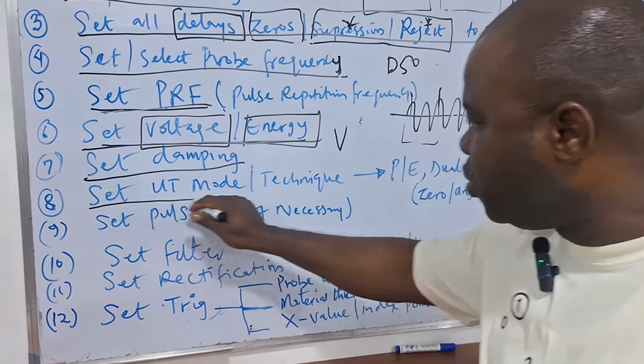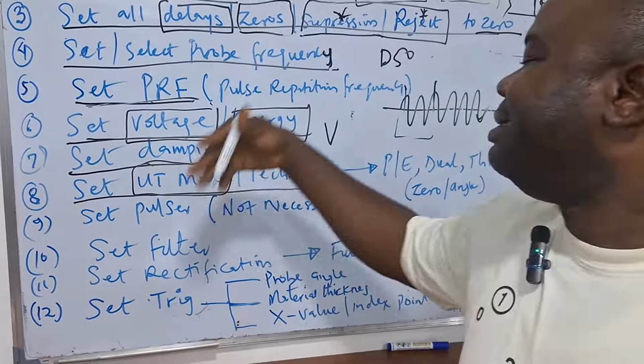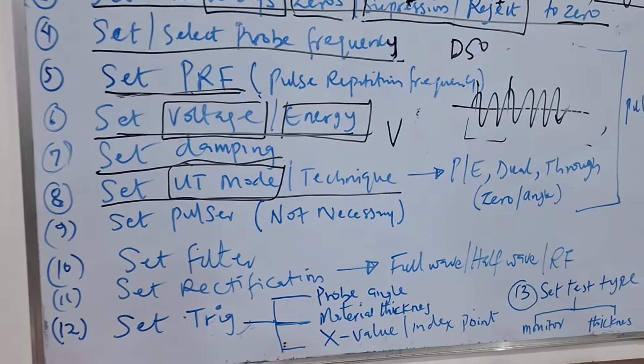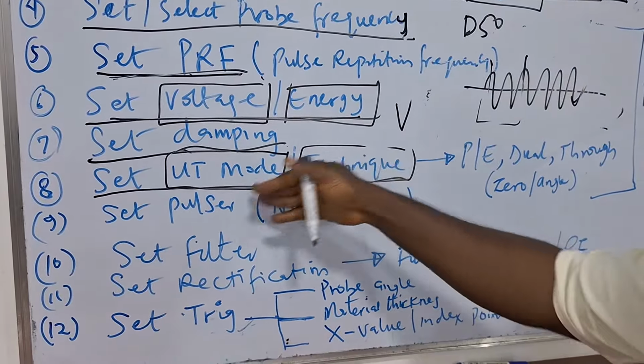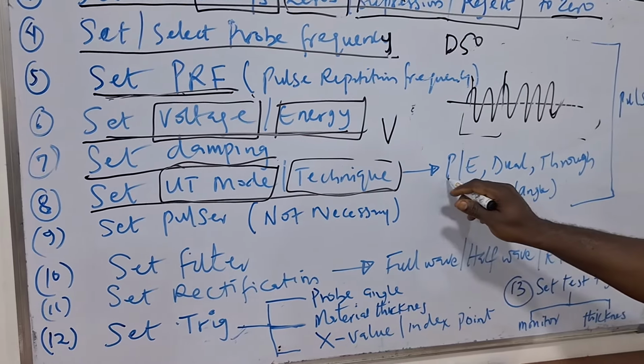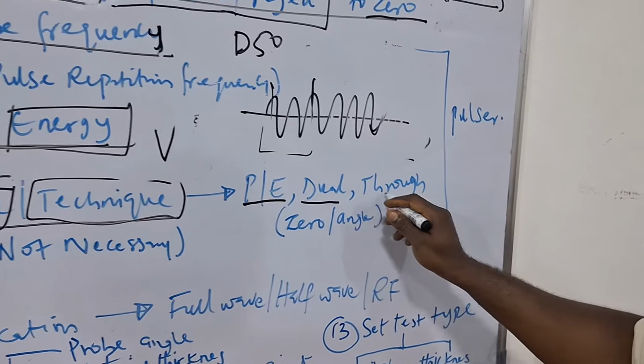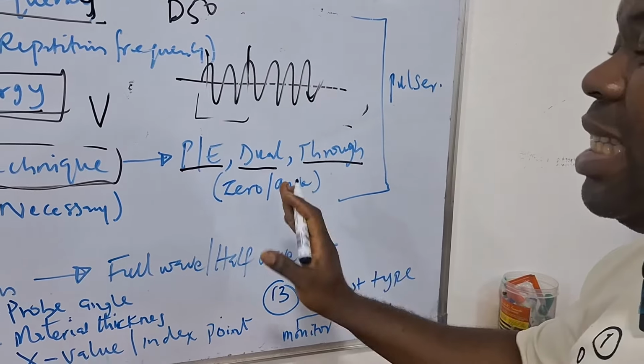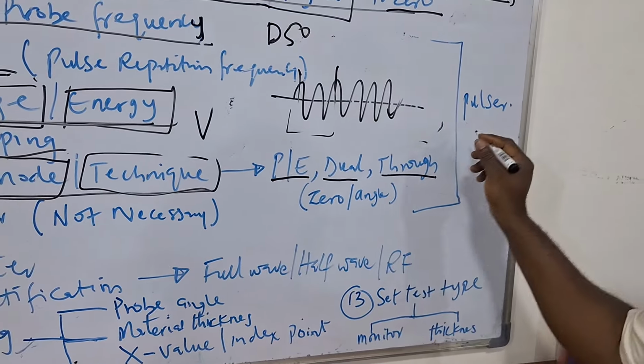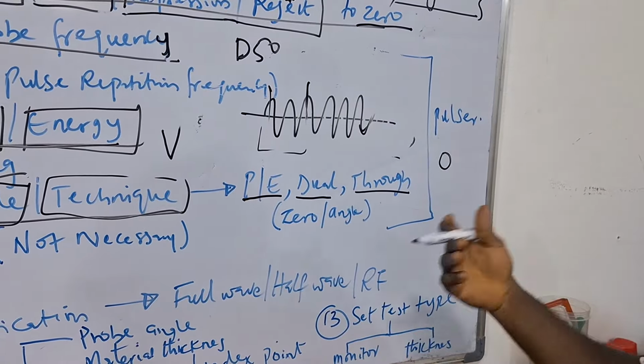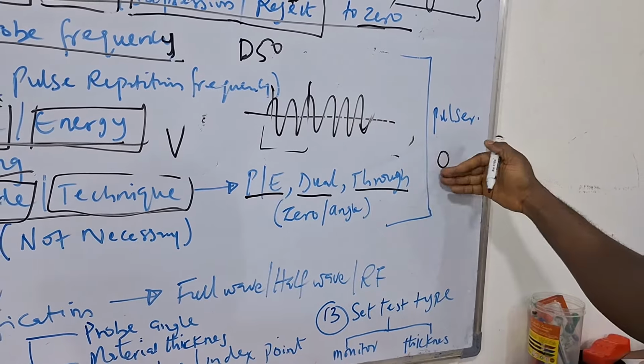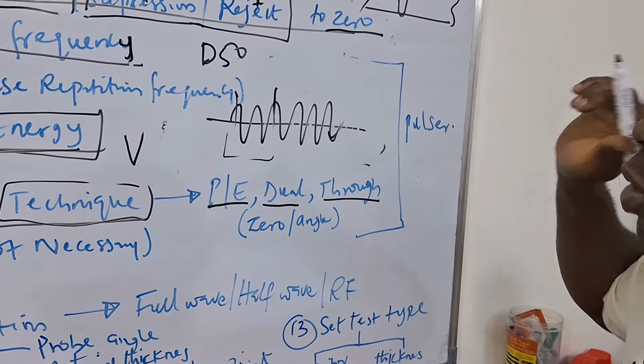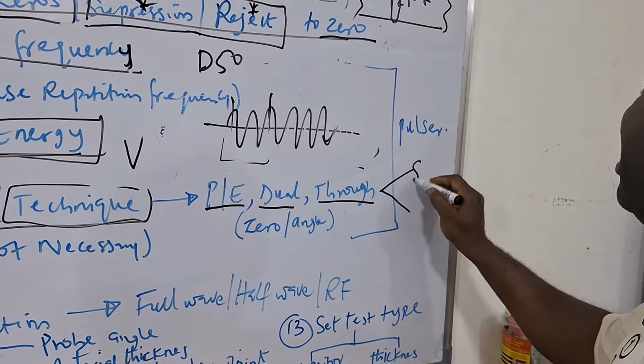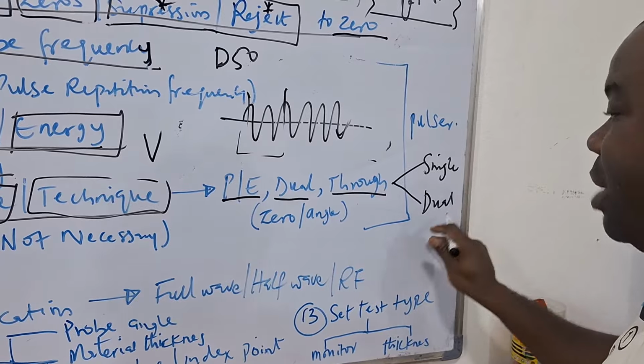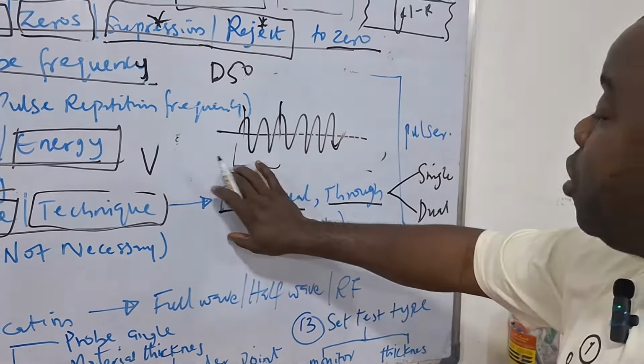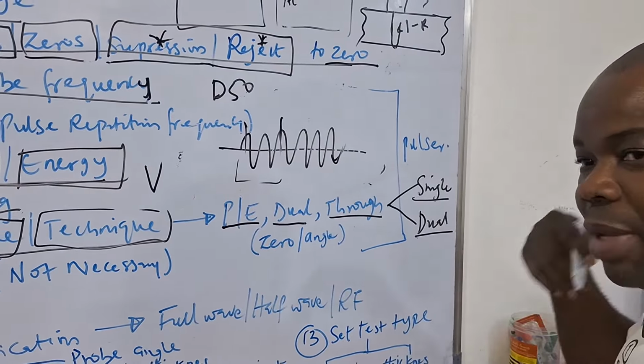The next thing you want to set is the UT test method. In some units, they will tell you UT mode or UT technique type. Depending on the nomenclature that is used, they are all asking you to select either your pulse echo, your dual, or your through transmission. In some units, they will not give you this. The general assumption is that when you see 0 degree, it's going to be pulse echo. Not really. But in some cases, they will not give you this option. Instead, they will give you either single element or dual element, not the angle.